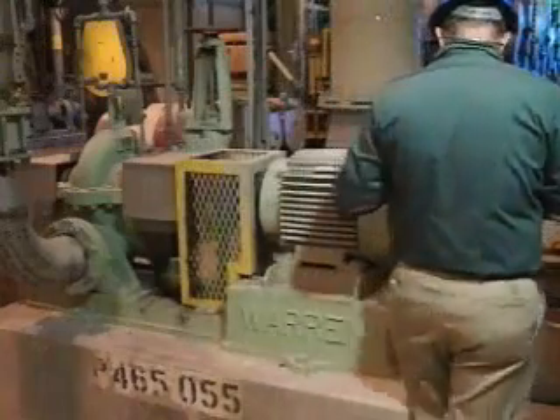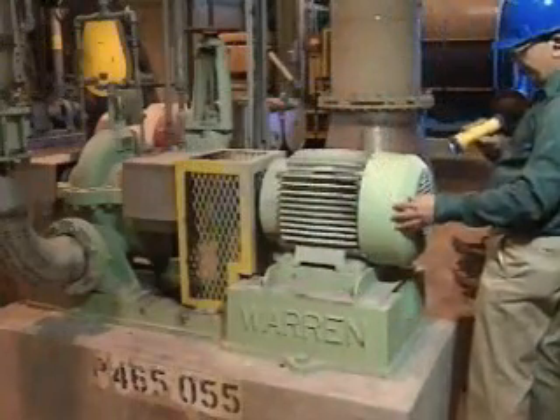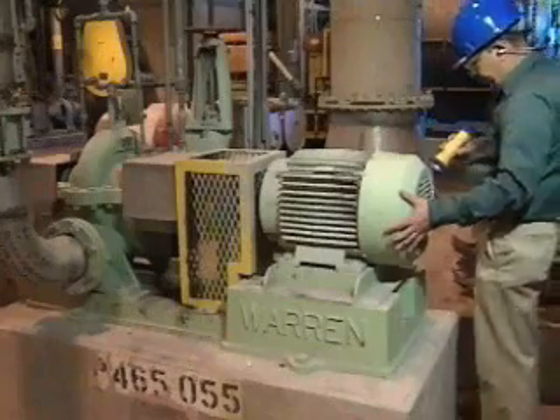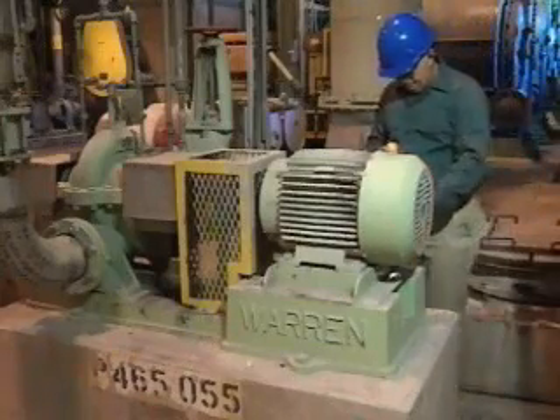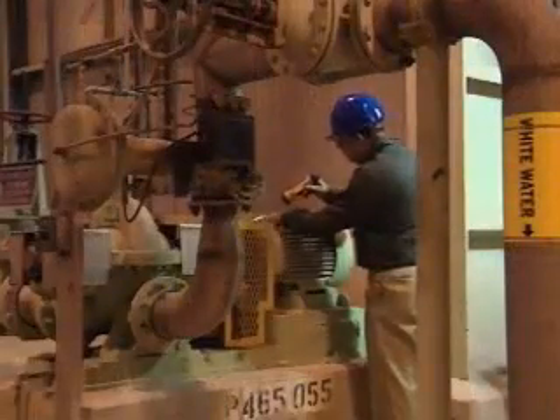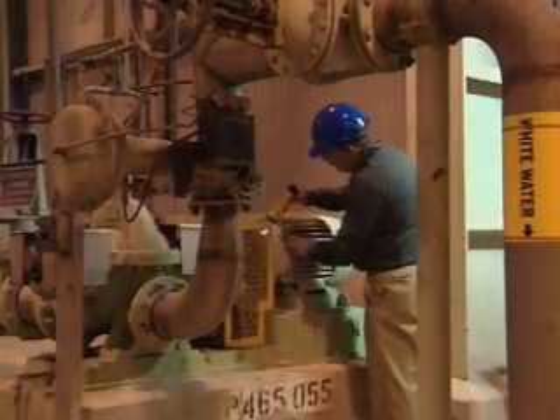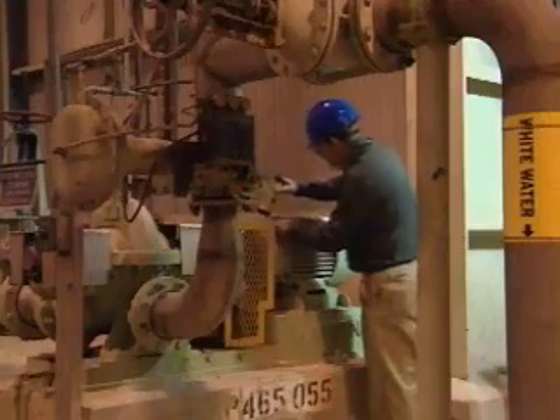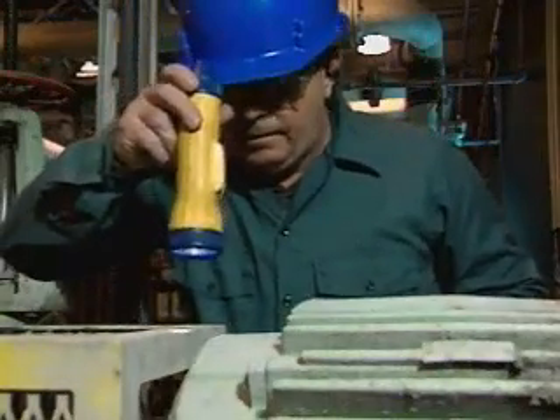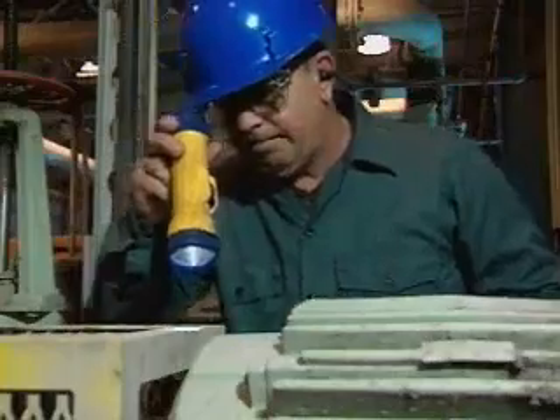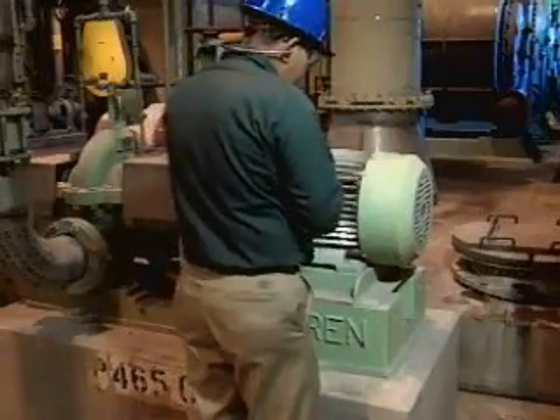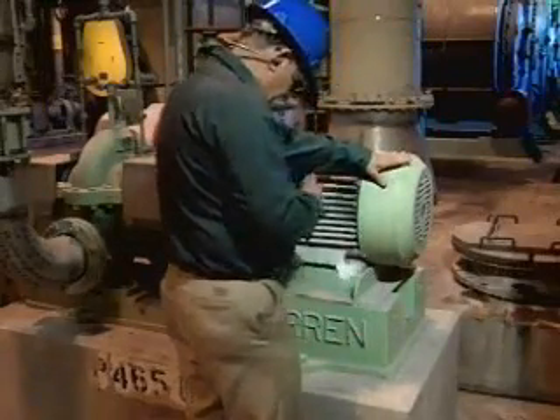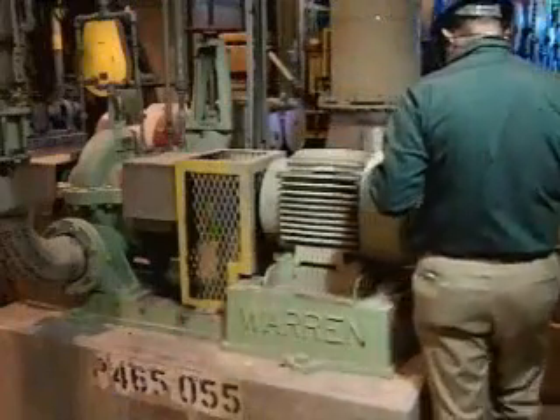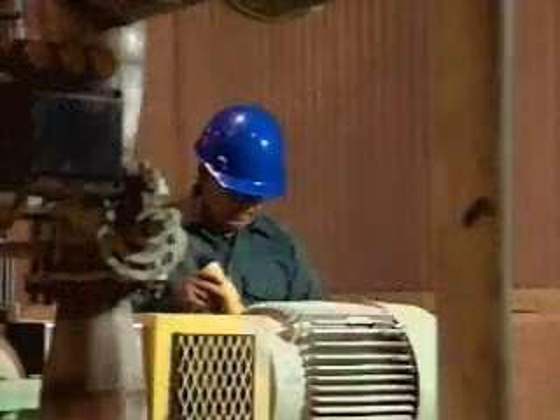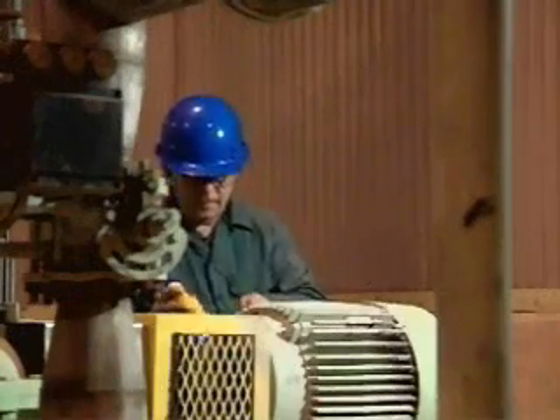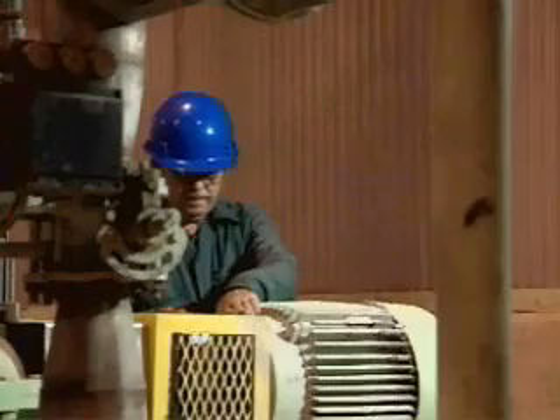Inspection is a very important part of the preventive maintenance program. By routinely inspecting equipment, you can determine if the equipment is operating as it should. If the motor is not running, begin your inspection by looking over the equipment, examining its general condition. Visually inspect the motor for any loose fastenings or broken parts. Check belts and pulleys to ensure that they are neither too loose nor too tight. Be alert to any wearing or fraying. If you find problems, tag out the motor in accordance with facility guidelines and make these minor adjustments.